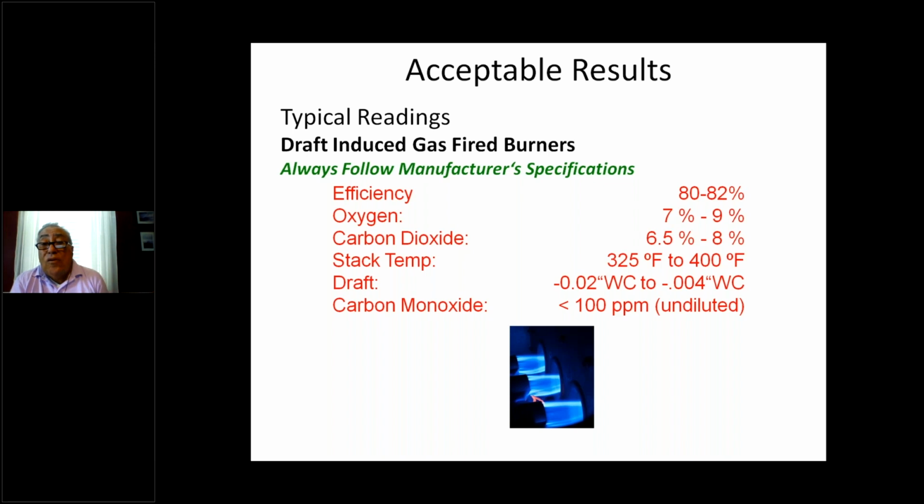And we're still looking to keep that draft manageable. So we're looking for 0.02, and I think I got an extra 0 in that 0.04 there. Just noticed that. But it should be 0.02 to 0.04. And again, we're looking for 100 parts per million undiluted carbon monoxide.